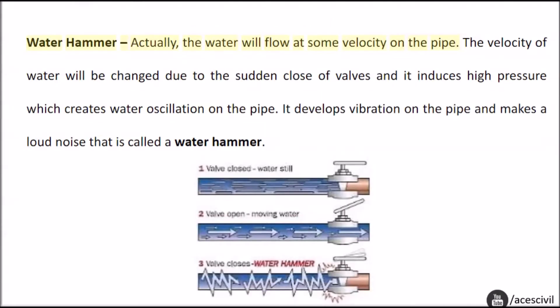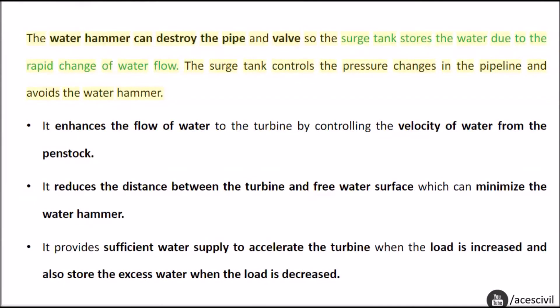Water hammer: the water will flow at some velocity on the pipe. The velocity of water will be changed due to the sudden close of valves and it induces high pressure, which creates water oscillation on the pipe. It develops vibration on the pipe and makes a loud noise — that is called a water hammer. The water hammer can destroy the pipe and valve, so the surge tank stores the water due to the rapid change of water flow.